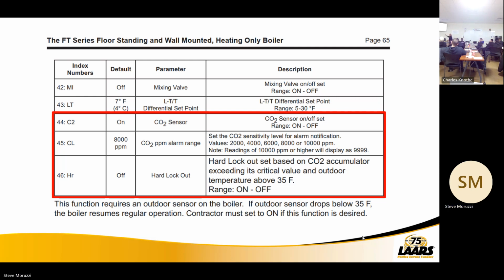So parameter 45, for 8,000 parts per million of CO2, okay? And if it sees it, you have an option, parameter 46, hard lockout or soft lockout, okay? So hard lockout is based on you have to have an outdoor sensor hooked up, which we give you, the outdoor sensor, guys. So what does that mean? That means if the temperature outside is above 35 degrees, and I'm cross-contaminated, you as a contractor can choose that as an on position. We'll lock that boiler out.